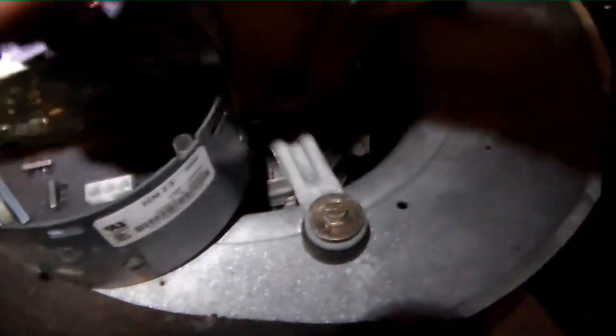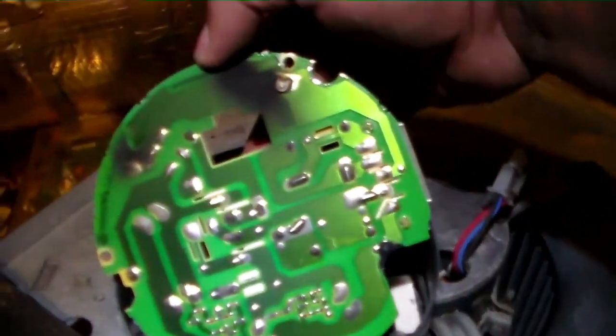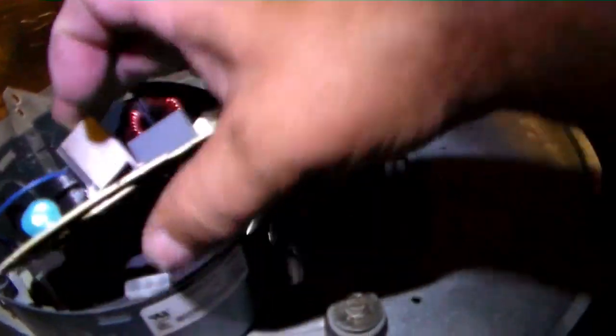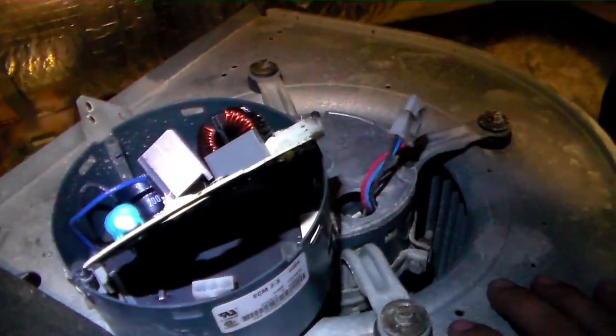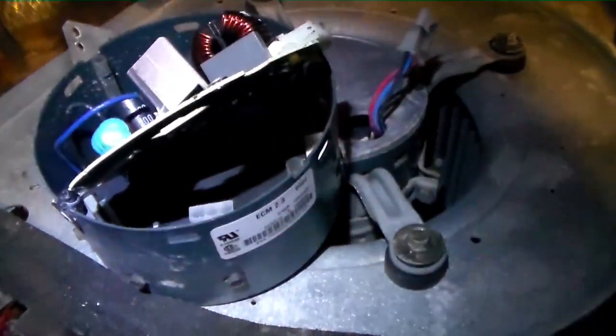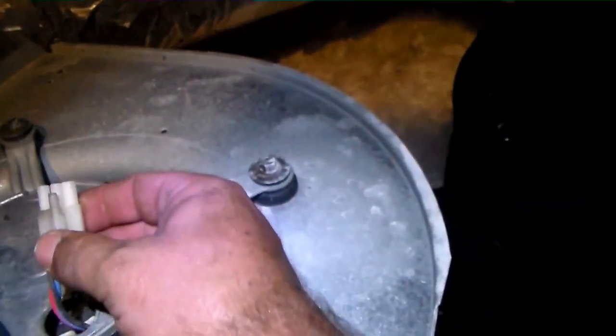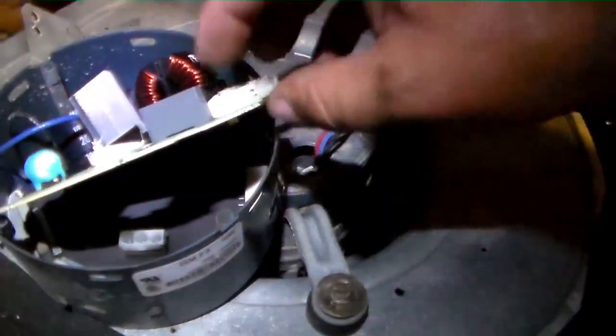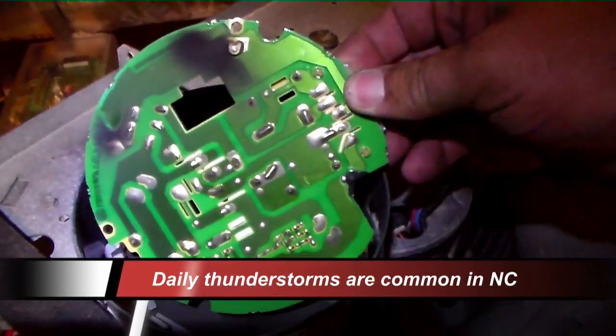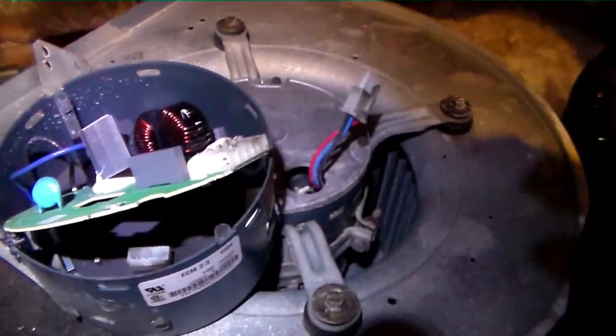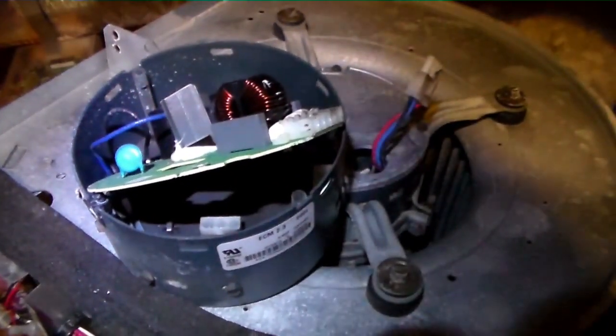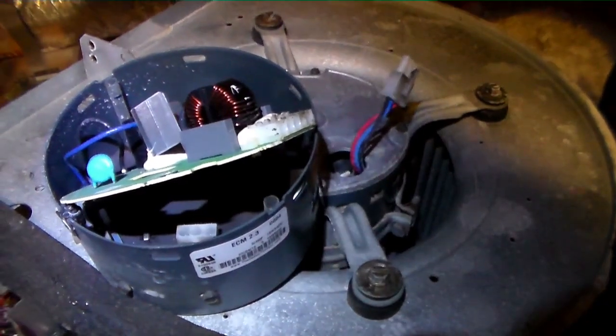I noticed two things when I came in here a little earlier. I see we have a ground screw there and we have a burn mark next to it. And when I flip over the control board in the module, you can see that there are burn marks heavily in the area where we have our ground. So I'm going to guess that we had a lightning strike, and this would be a great advertisement for those little surge protectors. You can see the darkened area here, but really, once you see where the ground screw was and flip it over, it's very, very damaged in that area. So that's going to be the cause of death for this motor, more than likely a lightning strike during one of our electrical storms.